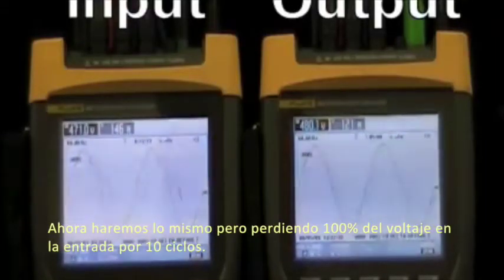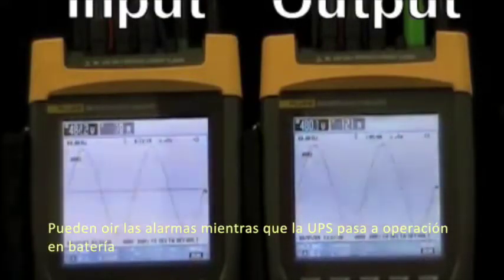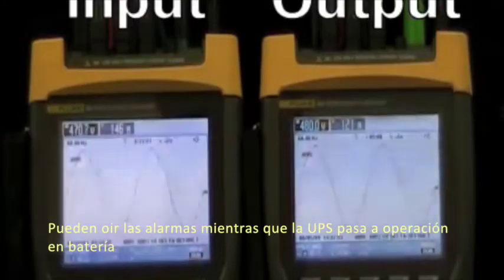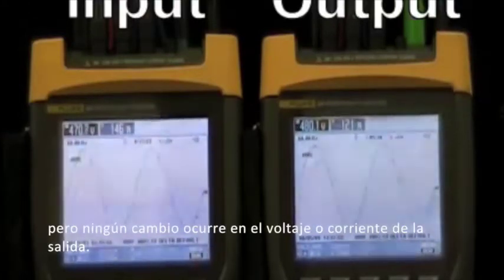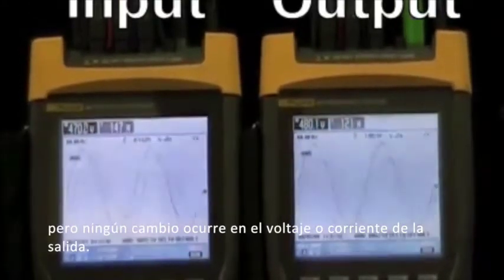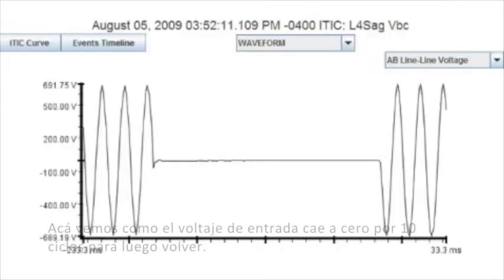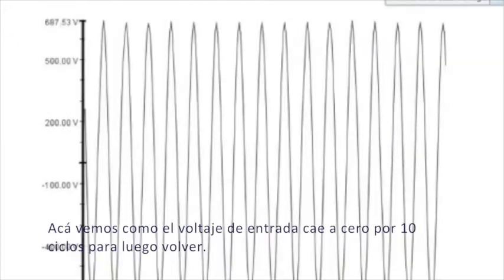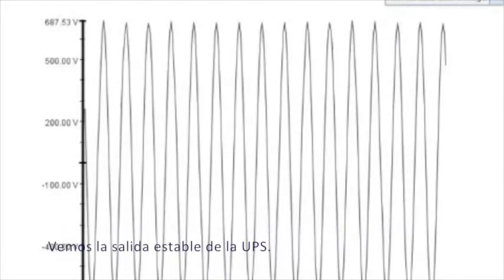Here we'll do the same thing, but performing a 100% loss of utility power for 10 cycles. You hear the alarms as the UPS goes to battery operation, but no change to the output voltage or current. Here we see the input voltage is dropped to 0 for 10 cycles and then returned. We see undisturbed output of the UPS.